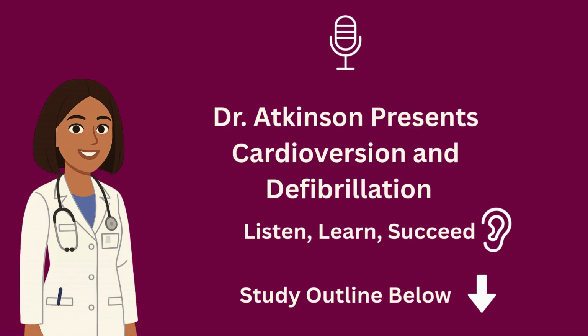Placement of the paddles or pads is also important. Standard placement is on the chest, but sometimes anteroposterior placement is used, with one pad on the chest and the other on the back, just left of the spine. Safety is key. We use only approved conductive mediums, never substitutes like ultrasound gel, and we make absolutely sure no one is in contact with the patient or equipment when a shock is delivered. Hands-off pads are preferred in many settings because they reduce the risk of accidental shock and make the process safer.